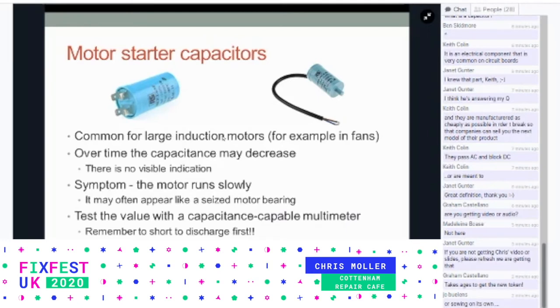These typically fail by going to a lower capacitance value. They might be 4 microfarads, 10 microfarads, something like that. When you test them, you find they're maybe only 0.5 or 1 microfarad. The symptom is that the fan runs slowly, and it's very tempting to think this is because of seized bearings in the fan, but it's also very likely to be because the capacitor has gone soft.